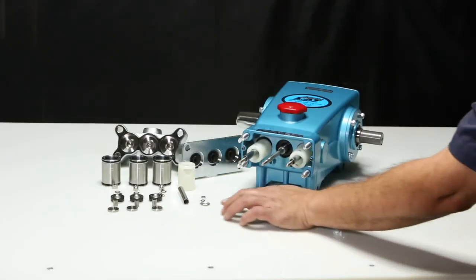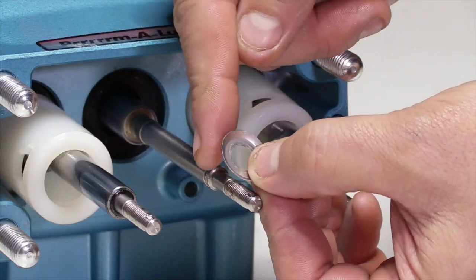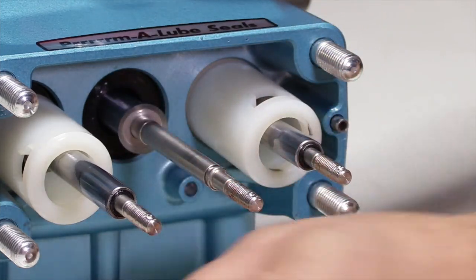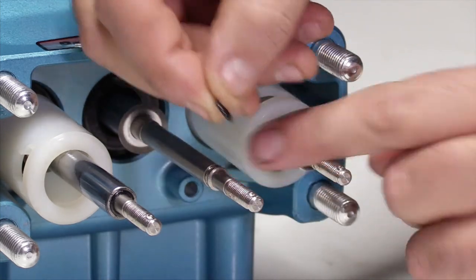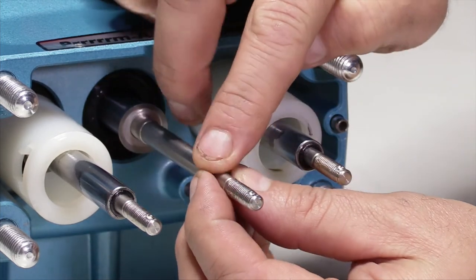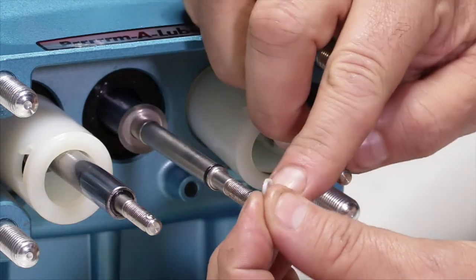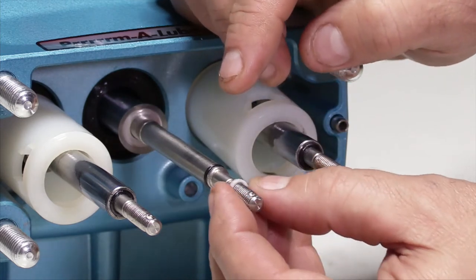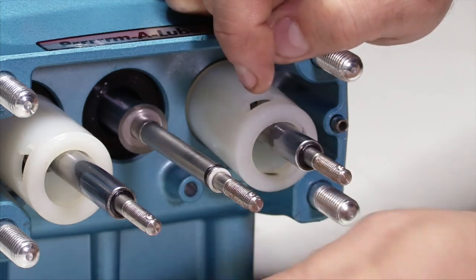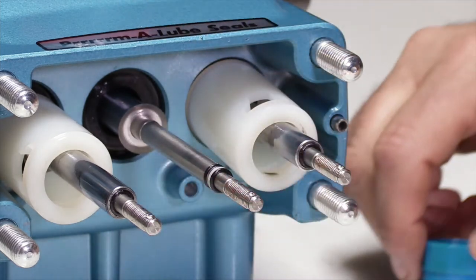To reassemble, begin by installing the barrier slingers with the curved dish side facing away from the crankcase. Install the first O-ring into the single groove side of the piston rod. Install the backup ring over the piston rod in position against the shoulder. Note, the backup ring does not go into the groove of the piston rod. Install the second O-ring against the backup ring. Exercise caution when sliding O-rings over the threaded ends of the piston rods as it could cause damage.